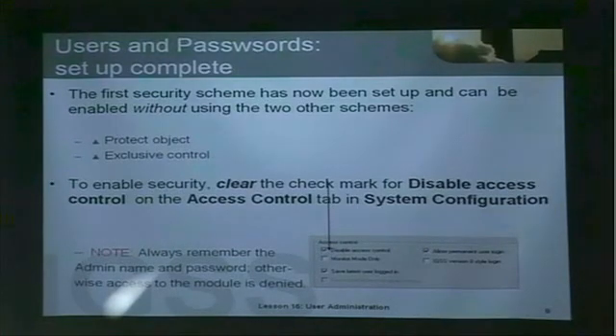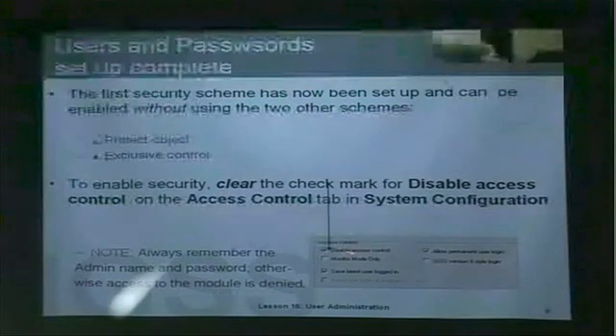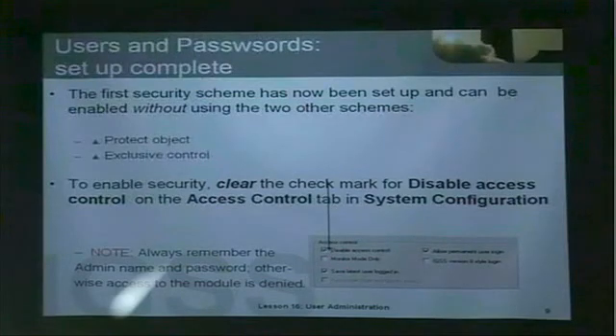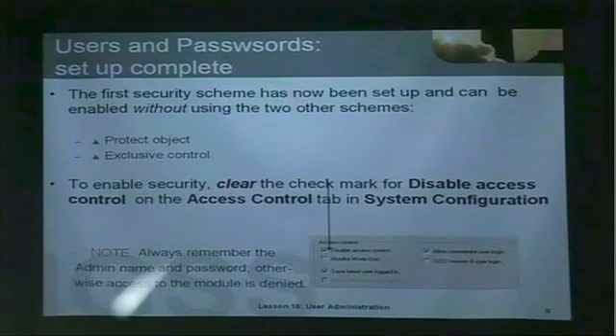After we configure all of our users, we are ready to use the security scheme. We do not have to configure the protect object level or the exclusive control level to be able to protect the configuration. One more thing to remember before using the user administration security module: go into the system configuration module, go to the access control tab, and remove the check mark that says disable access control. And remember to keep the password for a member of the admin group — otherwise, it will be impossible to come into the user administration module and alter settings.